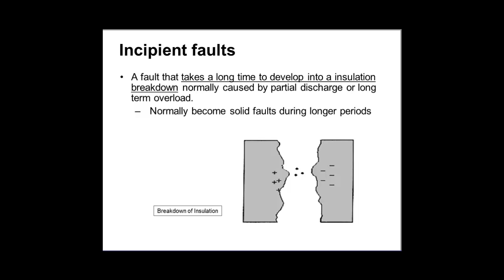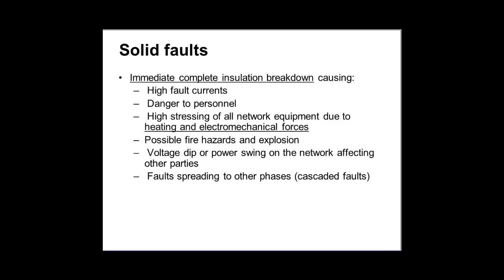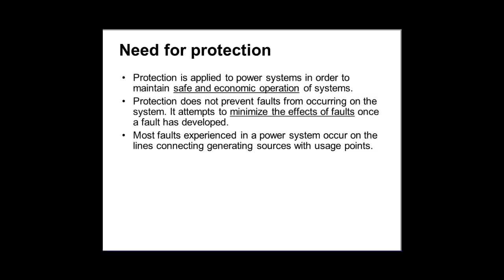Yes, nothing happened immediately. But it's more like decay in your tooth. Yes, that decay in your tooth is not happening in one day. It may take 6 months or 4 months or 3 months until the insulation material in your teeth degrades. This is exactly such a thing happening in cables and transformers. Maybe not now, maybe 6 months from now, 3 months from now, you will hear about that. That's the incipient fault. But solid fault, nope. It has got a very immediate result on the system, like a direct short circuit.